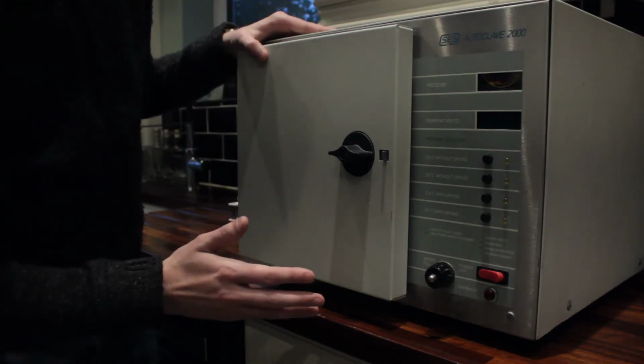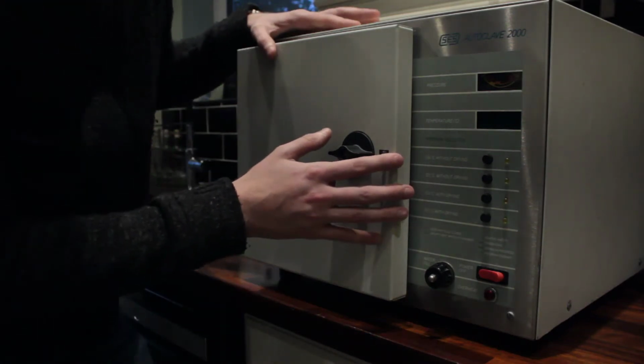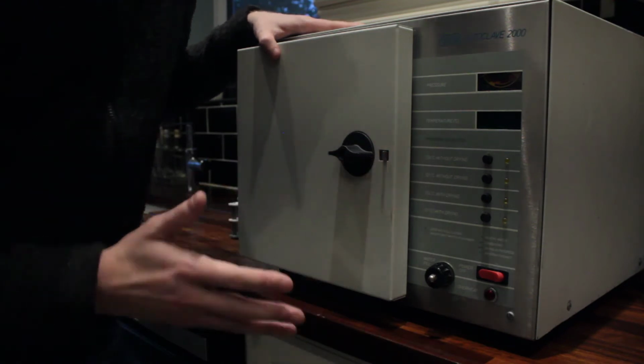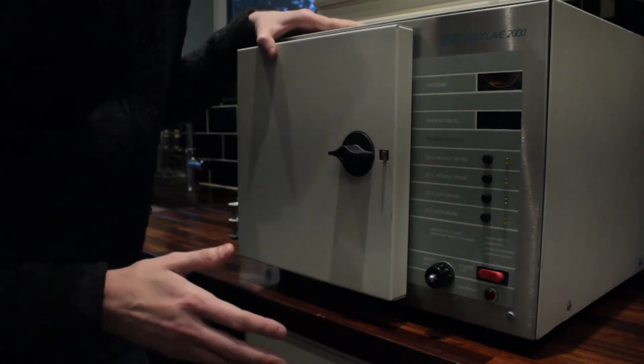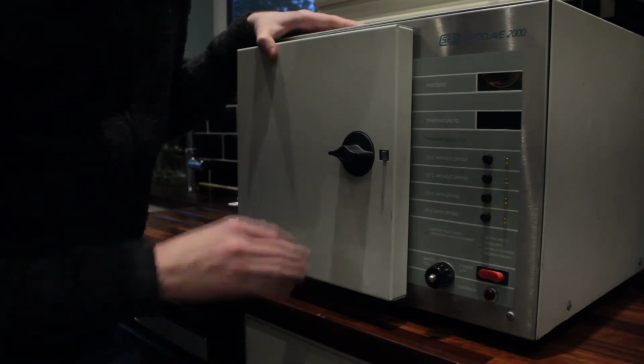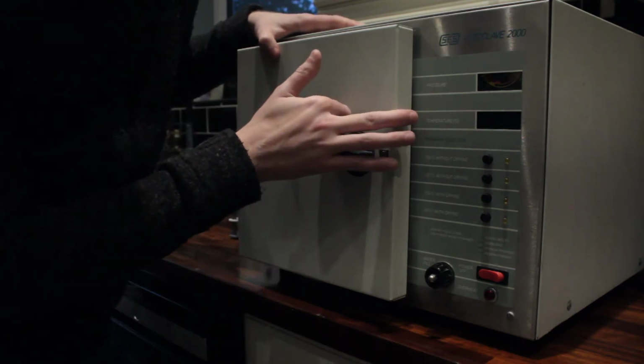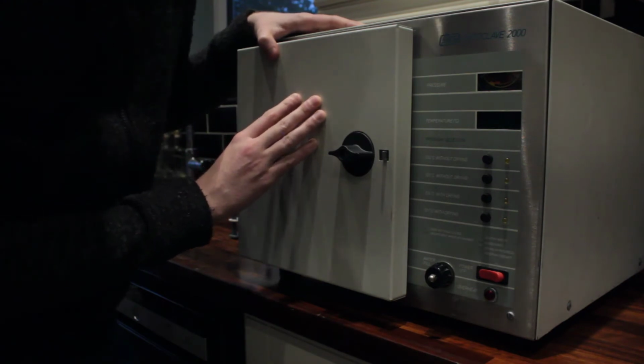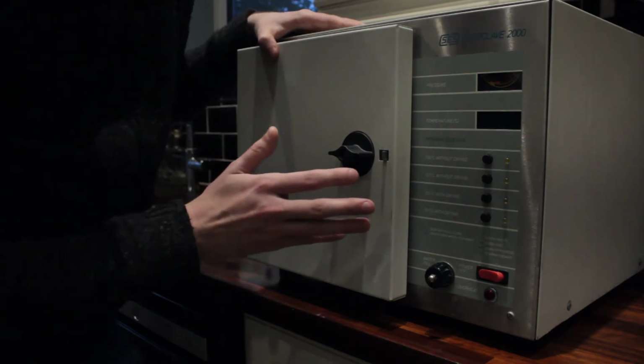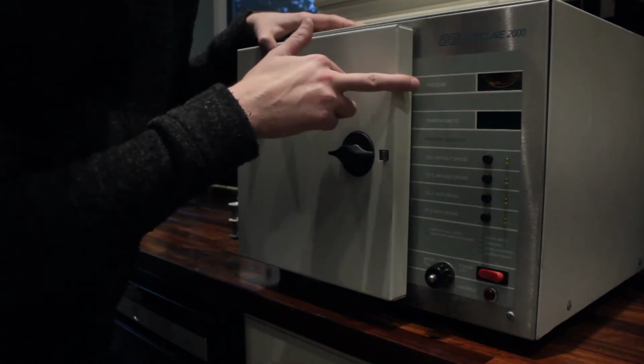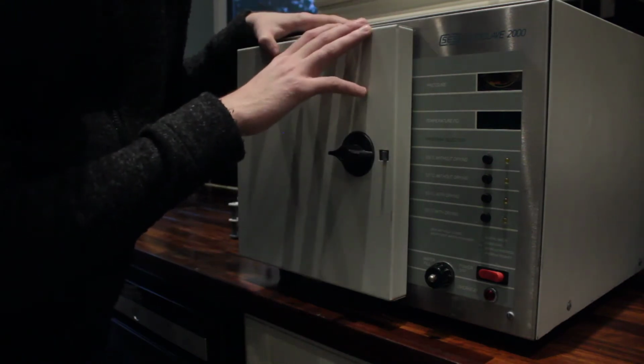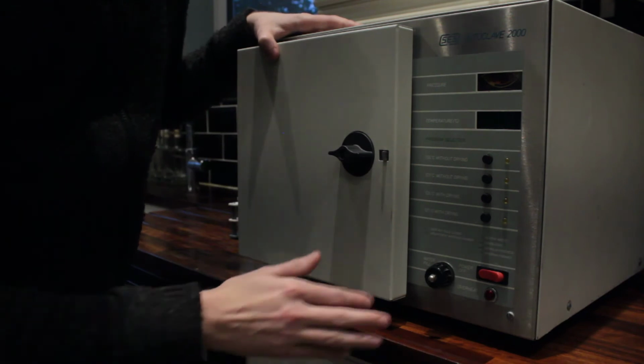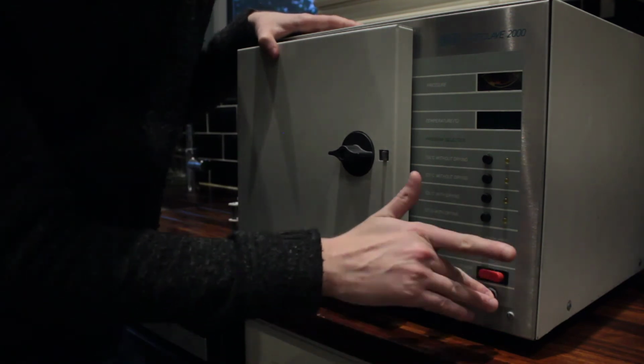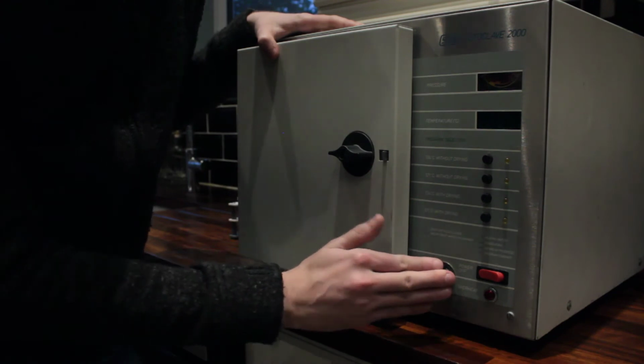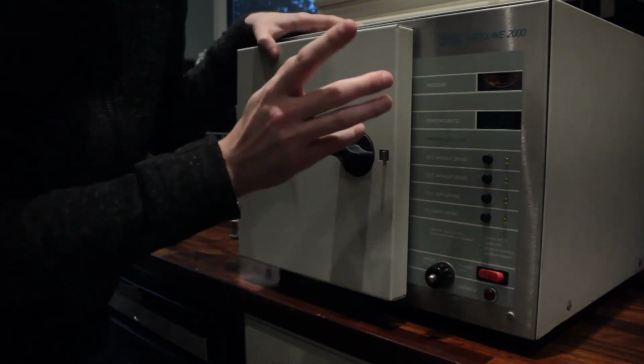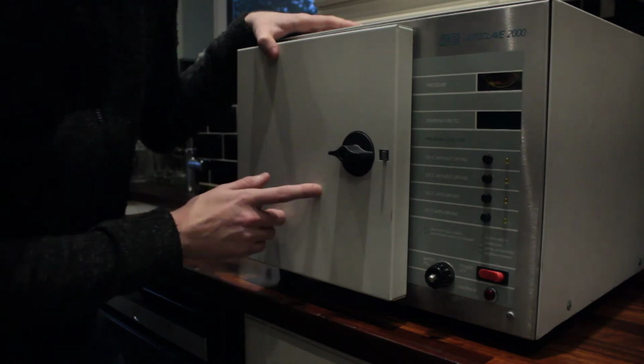On the control panel of the autoclave, we've got buttons for selecting the cycle that we want to use, both 121 and 134 degrees Celsius with and without drying. We've got a temperature gauge which will show us the temperature inside of the chamber and will also tell us what part of the cycle we're on. There is a pressure gauge to show us the pressure within the chamber, and then we've got a power switch, an overheat indicator, and we have the valve for allowing water from the reservoir into the chamber.